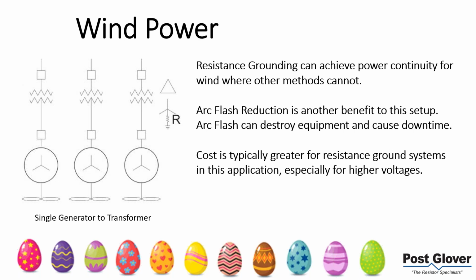Just in terms of some benefits in this application for resistance grounding, just in case it wasn't clear, the effective grounding is essentially solid grounded. There's some benefits, and we'll go over those, but it's very similar to that. It's allowing those over voltages to be somewhat suppressed, and so that's the difference. But that being said, resistance grounding, if you need continuity for your wind power, that's unique to resistance ground, specifically high resistance ground typically.